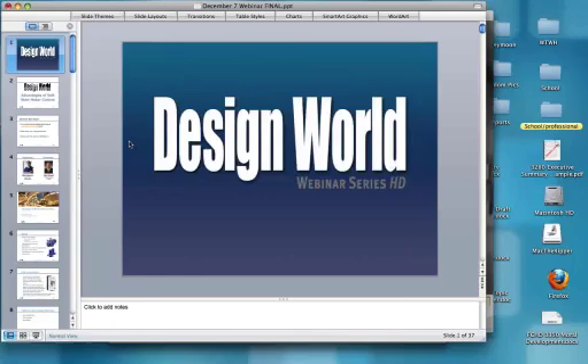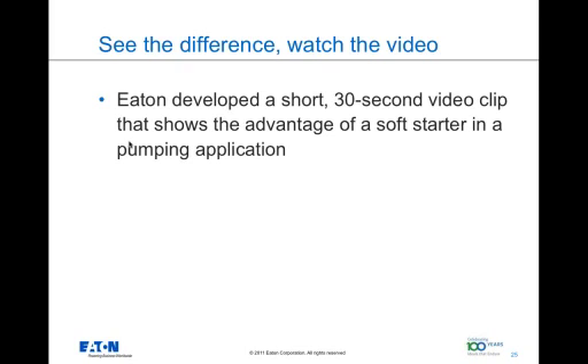For this very reason, a lot of the pump customers are actively switching to soft starters. They have the municipalities, for example, who are the owners of a lot of pumps. They have put up specifications where beyond a certain horsepower, a soft starter needs to be definitely used. In Florida, for example, the municipalities dictate that anything over 50 horsepower needs to be a soft starter. And the reason they did that is to eliminate the water hammer effect in the system and the resulting check valve slamming.